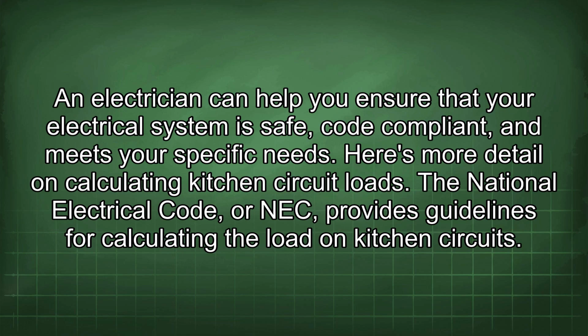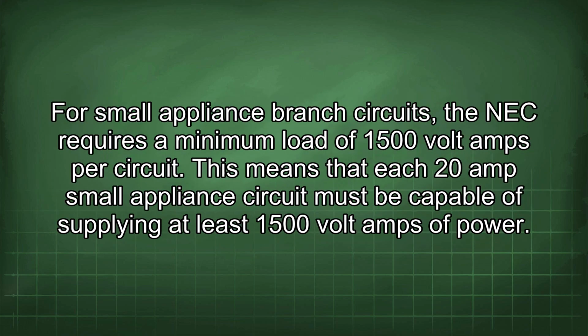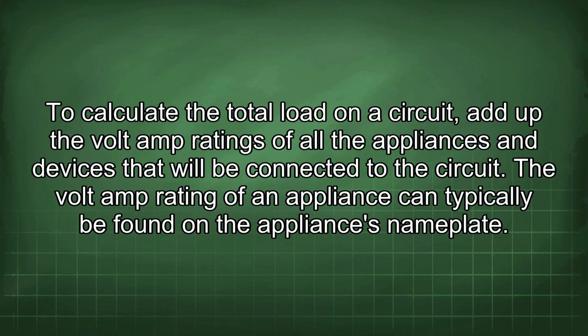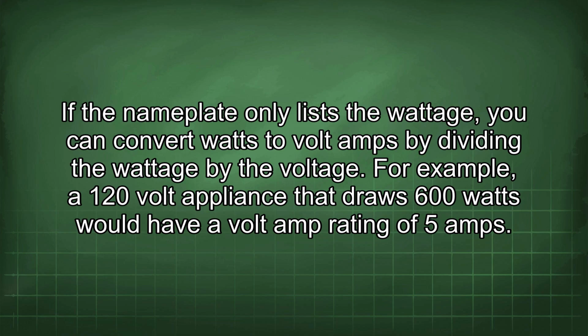The National Electrical Code, or NEC, provides guidelines for calculating the load on kitchen circuits. For small appliance branch circuits, the NEC requires a minimum load of 1500 volt-amps per circuit. This means that each 20-amp small appliance circuit must be capable of supplying at least 1500 volt-amps of power. To calculate the total load on a circuit, add up the volt-amp ratings of all the appliances and devices that will be connected to the circuit. The volt-amp rating of an appliance can typically be found on the appliance's nameplate. If the nameplate only lists the wattage, you can convert watts to amps by dividing the wattage by the voltage. For example, a 120-volt appliance that draws 600 watts would draw 5 amps.